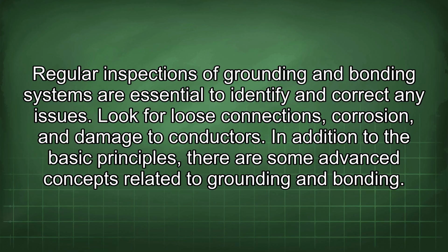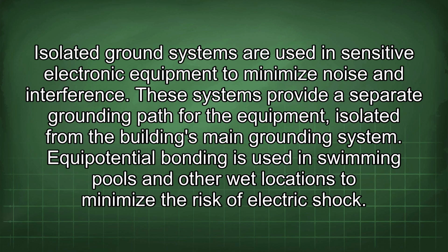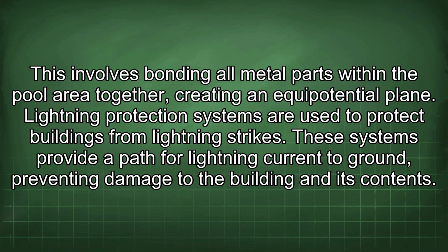In addition to the basic principles, there are some advanced concepts related to grounding and bonding. Isolated ground systems are used in sensitive electronic equipment to minimize noise and interference. These systems provide a separate grounding path for the equipment, isolated from the building's main grounding system. Equipotential bonding is used in swimming pools and other wet locations to minimize the risk of electric shock. This involves bonding all metal parts within the pool area together, creating an equipotential plane.